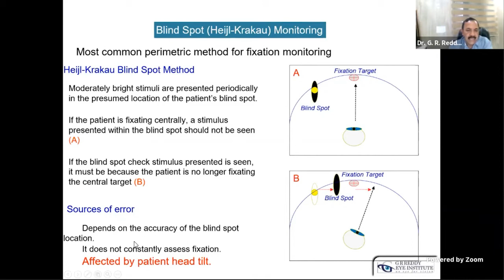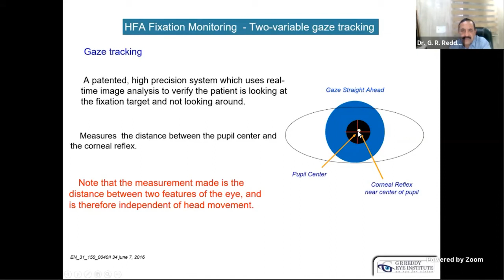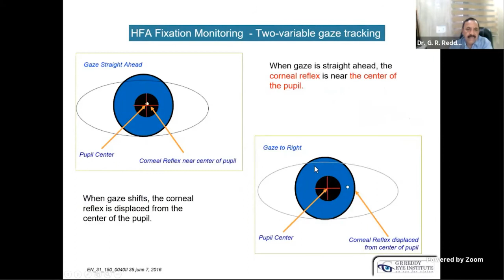The main disadvantage of the blind spot method is that head tilt will affect the fixation losses, and there is no continuous gaze monitoring to know whether he is fixing properly or not. In gaze tracking, we have two variables, the center of the pupil and the corneal reflex. They correspond to each other when the patient gazes properly. When the eye moves, they deviate from each other.